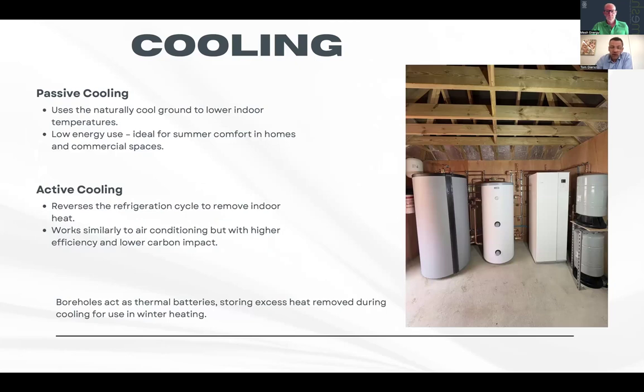That is becoming quite popular with large, high-end residential properties. You can do two versions: passive cooling, where you are not engaging the compressor, you are just transferring the heat from the property into the boreholes. You can then use, let's say, underfloor heating to gently distribute that cooling energy. It's not as efficient, but it provides some cooling capacity. Or active cooling, where you actually use a compressor to extract the heat from your cooling system, and it moves the heat to, let's say, a heating buffer tank, or can heat your swimming pool or any other area that you might need heated. Or if there is an excess of energy and the heat pump cannot utilize it, it will discharge that excess energy into the borehole. So that's called active cooling.